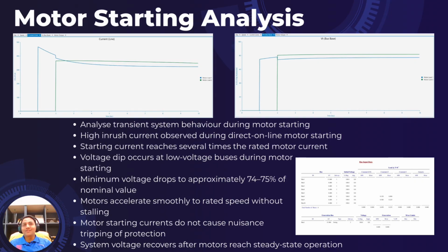Alright, next is motor starting analysis. For the motor starting analysis, we look at what happens to the system when the large motors are switched on. From the results, we can see that when the motors start, they draw a very high current for a short time. This high current causes the voltage at the low voltage bus to drop, and during the starting of motor load 1, the voltage goes down to around 74 to 75% of the normal value.